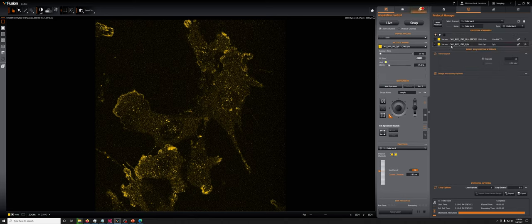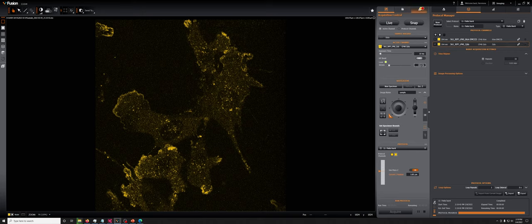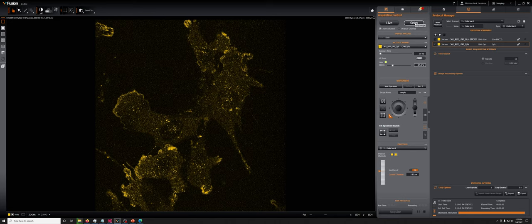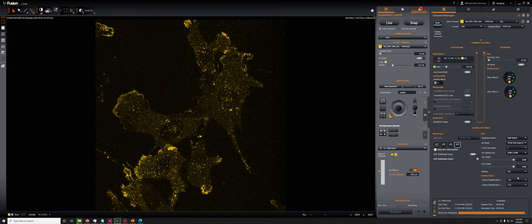So let me show you what the Zyla would look like using the exact same conditions. So if I go to 10 milliseconds and 25% laser power and just snap an image. And actually, let me bin the Zyla to make it more comparable. So the pixel sizes are the same. So this is what you get with the Zyla. So you can see that the Zyla, even kind of matching all the conditions to the EMCCD, it has a lot of trouble with very short exposures. And the reason for that is that the Zyla has a certain amount of readout noise.